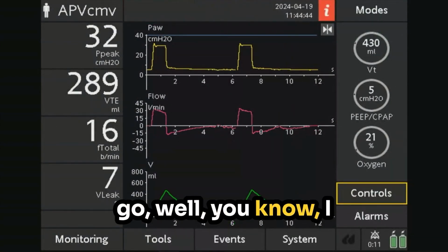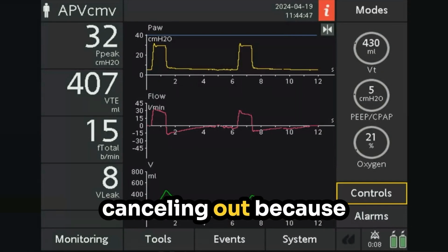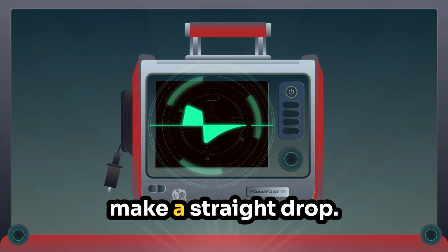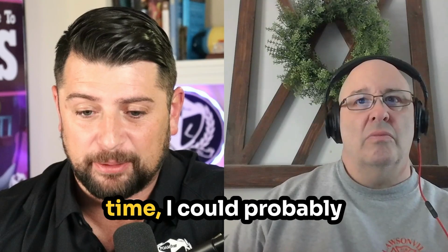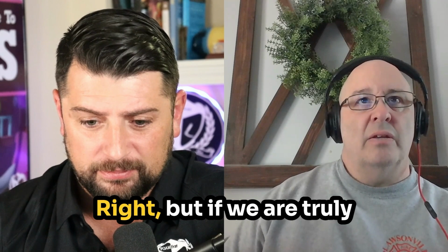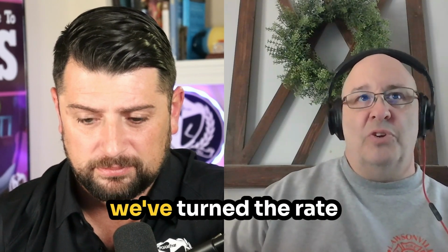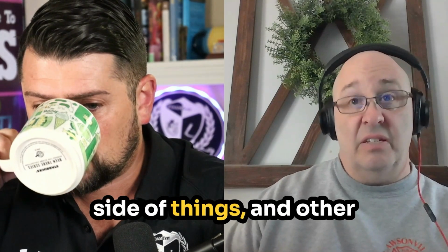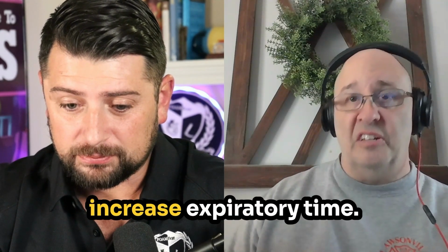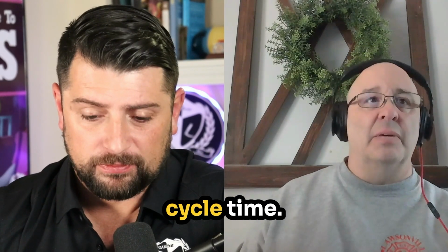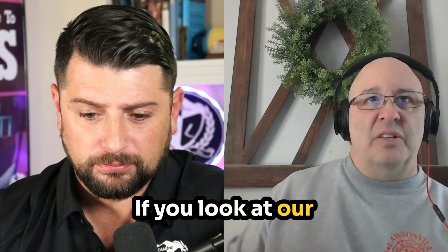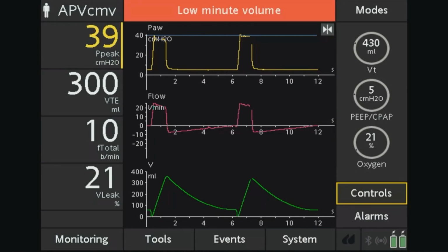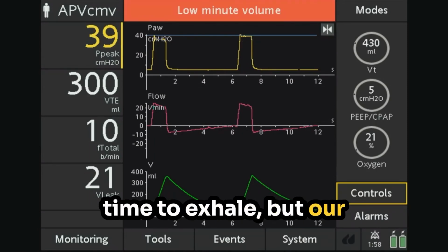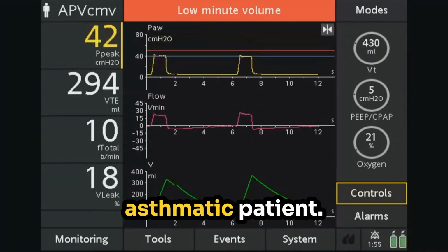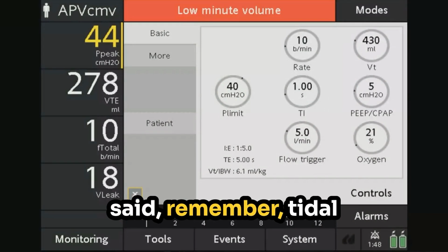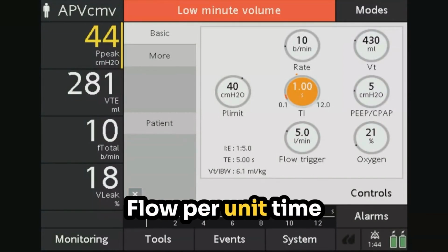When I look at that, I go, well, I could see now that inspiratory wave is cancelling out because of the I time, right? Whenever I see that inspiratory line make a straight drop, I always think, well, if I increased my I time, I could probably get a little bit more volume out of that. Right. But if we are truly doing an asthmatic now, we've turned the rate down to fix the expiratory side of things. And other than a disconnect, that is the fastest way to increase expiratory time. Turn your rate down, you're changing cycle time. That is the fastest way. If you look at our example now, we've provided enough time to exhale, but our exhale tidal volumes are not where we want them to be for this asthmatic patient. Your best option, as you said, remember, tidal volume is flow and time. Flow per unit time equals volume.